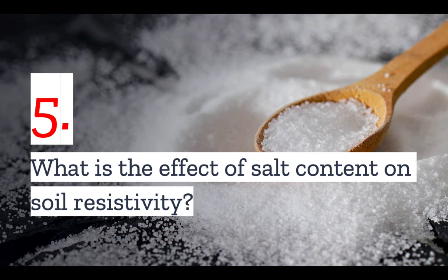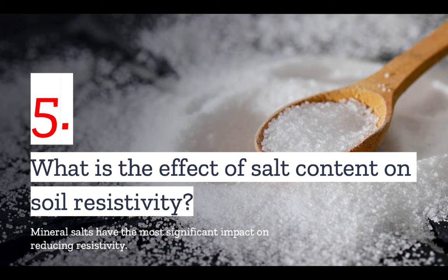Number five: what is the effect of salt content on soil resistivity? Well, it's a big one, because you aren't able to achieve low resistivity with soil alone. Soil must also contain mineral salts as a way to form an electrolyte to conduct electricity. Therefore, mineral salts have some of the most significant impact on reducing resistivity, which means soil resistivity is a good way to check for saltwater inundation, and if you're looking to treat a soil to improve its electrical characteristics, mineral salts are the first choice for treatment.